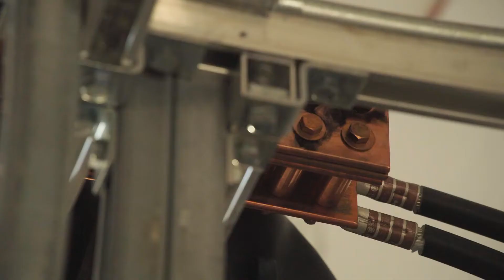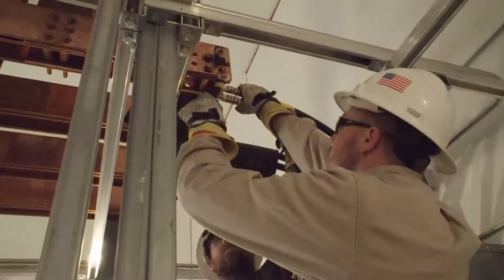It was a Tuesday. We were scheduled to go to 701 Colorado and energize a 1200 amp disconnect with jumpers, and we were going to land those jumpers on a hot energized 480 bus bar. The jumpers were already in the vault, we just had to land them on the bus. We covered up everything that we thought could become energized. While we were landing the jumper, we had the jumper landed, we went to tighten our bolts. He told me what bolt he had his wrench on. I put my ratchet on the other bolt. He had turned just for a second, and when he turned, he bumped the strut.